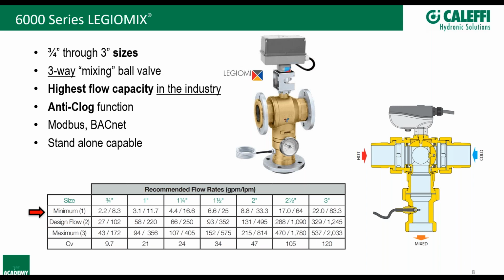And the reason why we can eliminate recirc creep is the fact that we're using a three-way ball valve inside of here. So a three-way ball valve obviously has the ability to completely close off one side or the other. So that way you're eliminating the idea that you can add more heat to the loop than what it actually needs. So really cool product we've had out for a few years now in the North American market. It's been in the European markets, South America, and the Middle Eastern markets for almost 2 decades. Available in 3/4 inch through 3-inch sizes.